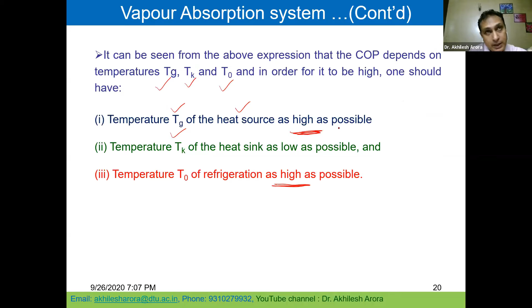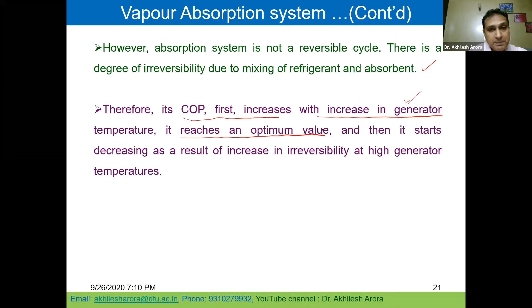Therefore, its COP first increases with the increase in the generator temperature. What you have heard just now is that the temperature of the heat source should be as high as possible, so I would like to operate the absorption system at the highest temperature and keep on increasing the temperature. But what is going to happen? The COP will first increase with the increase in the generator temperature. It reaches an optimum value, a maxima, and then it starts decreasing as a result of increase in irreversibility at high generator temperature. And this irreversibility, if you have studied thermodynamics, you can understand comes because of the finite temperature difference.